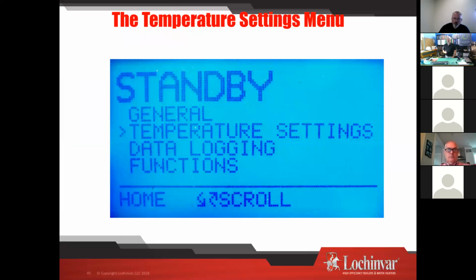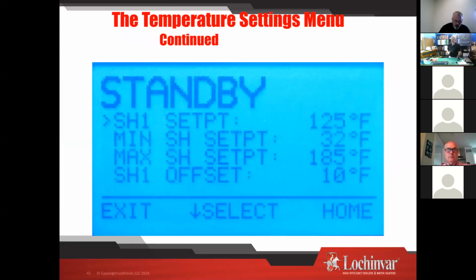All right, just talk a little bit about temperature settings here. All right, so just some terminology we'll go through, and notice the one, SH1. So there's 3 set points. I can set all 3 set points different, okay? So space heat 1, I have a minimum and maximum space heat set point. So that minimum maximum, that's my operating window, if you will.